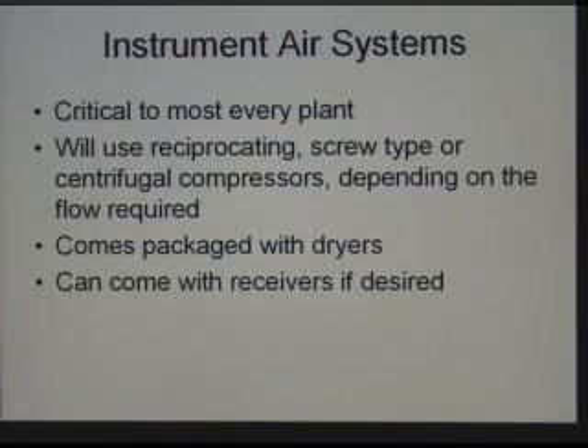Instrument air systems. Well, they're critical to most every plant. I haven't seen too many plants that don't use air as part of actuation systems for valves, especially isolation valves, your shutdown valves. And so we'll buy air systems to either supplement existing air systems or new systems to put into new facilities. And so we'll use either a reciprocating or a screw type or a centrifugal type of compressor depending on the flow rate required. If it's a small plant or it's an existing plant that needs a small supplement, then we'll go with a reciprocating kind of compressor. Relatively inexpensive, but we're not talking very high flow rates and very high pressure ranges here.